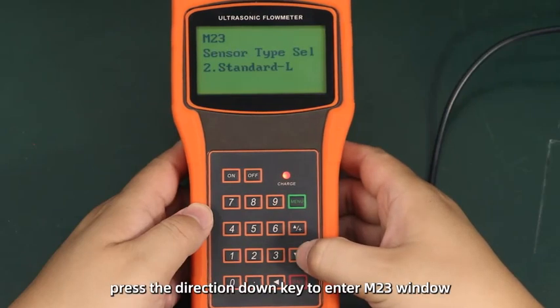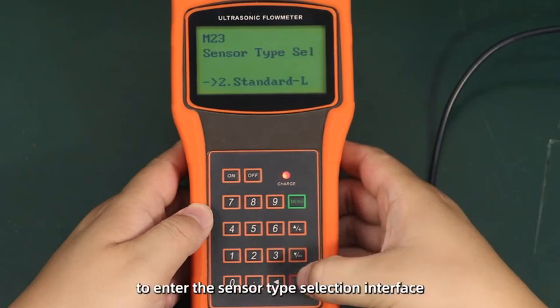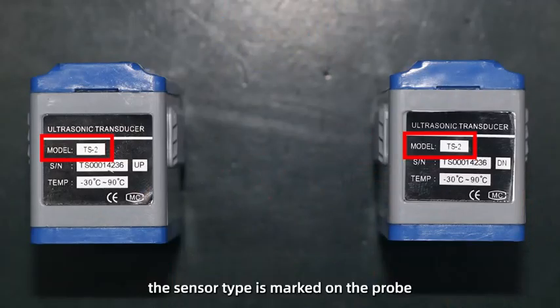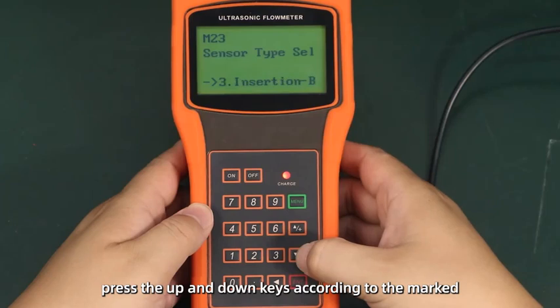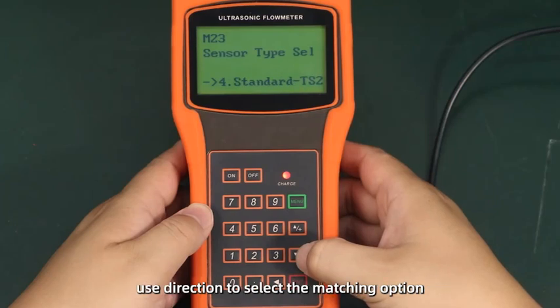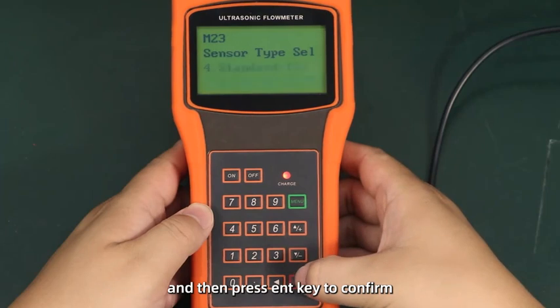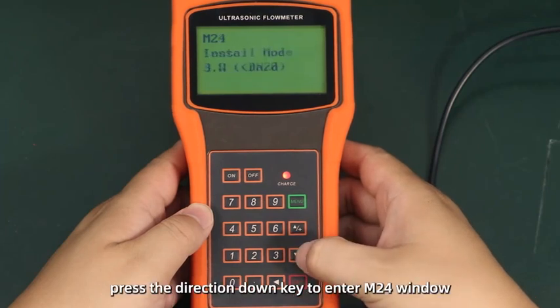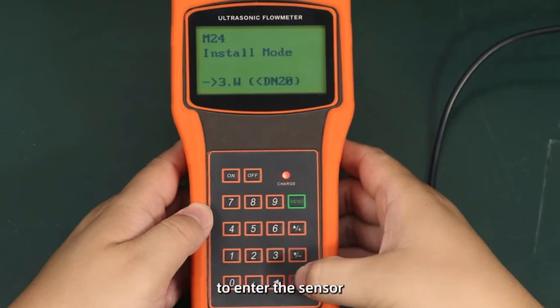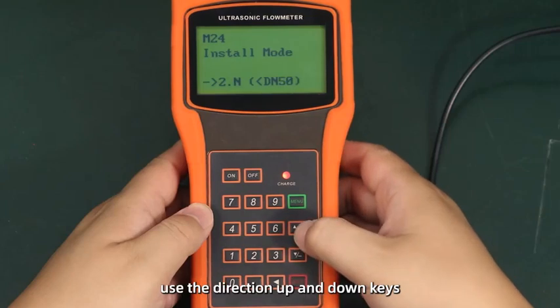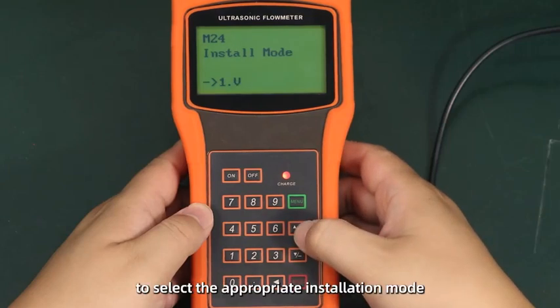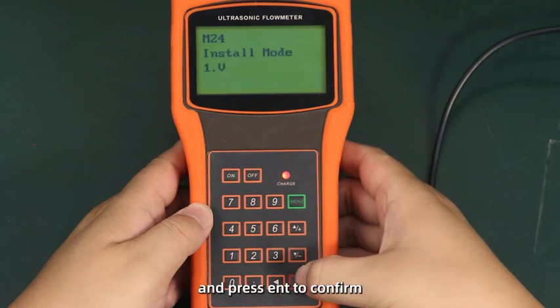Press the direction down key to enter M23 window, and press ENT key to enter the sensor type selection interface. The sensor type is marked on the probe. Press the up and down keys according to the marked use direction to select the matching option, and then press ENT key to confirm. Press the direction down key to enter M24 window. Press ENT key to enter the sensor installation mode selection interface. Use the direction up and down keys to select the appropriate installation mode, and press ENT key to confirm after the selection is completed.